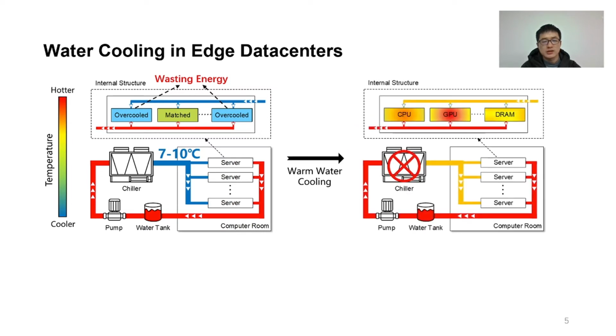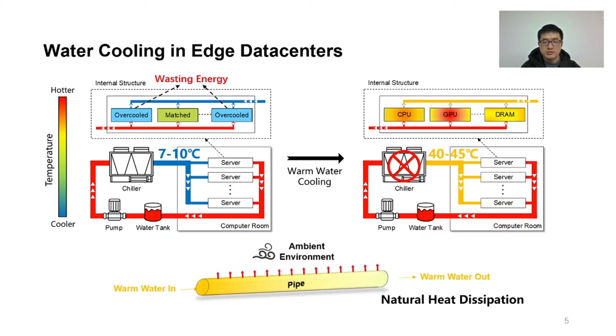Recently, warm water cooling has been proposed to save the cooling energy by reducing the use of the chiller. Since the water temperature can reach 40 to 45 degrees Celsius, that is higher than the ambient temperature, the water flowing in pipes and tanks can disperse the heat directly to the ambient environment. By leveraging this natural heat dissipation phenomenon, less energy will be consumed by the chiller. However, although it's less likely to overcool any hardware component and save the cooling energy, some high utilization components, known as hotspots, can be overheated. This may degrade hardware performance, shorten hardware lifespan, and even lead to system breakdown.